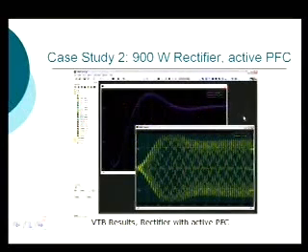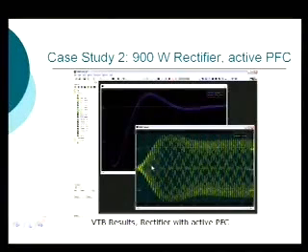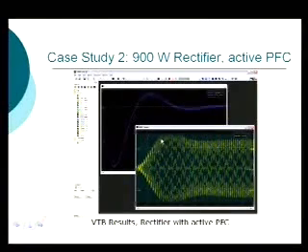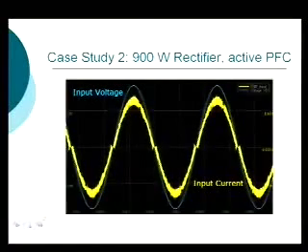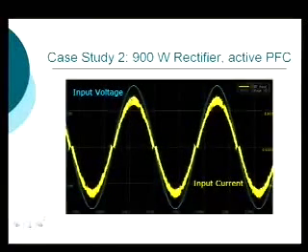Looking at the input quantities, the cyan is the input voltage and the yellow is the input current. You can see it has some envelope related to startup, but at every instant it looks sinusoidal. Zooming in on the input current and comparing it to the input current with no power factor correction, you can see it's very sinusoidal, and it appears to be pretty much in phase as well.